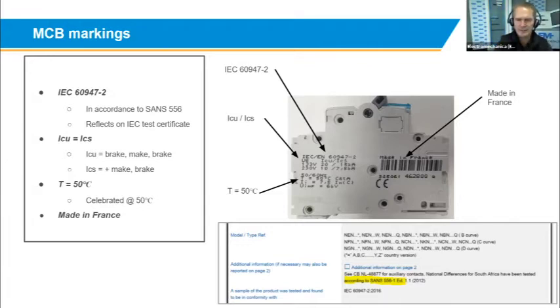This was a snapshot from the NRCS test certificate. Then it mentions there Icu equals Ics. Also, a good thing to know is that your product is rated at 10 kA. Icu equals Ics. So with Ics, normally you get a fault in your product, it trips, you go and switch it back on onto that same fault in the line, and it opens again safely. That rating is the first rating on your product, rated at 10 kA. Then you close it a second time, and it opens for a third time. What it means is that on that second close and third break, the fault level on that product still stays 10 kA. If it reads Ics equals 50% of Icu, it means that on the second close and the third break, that product is not rated at 10 kA anymore, but has dropped to 5 kA.